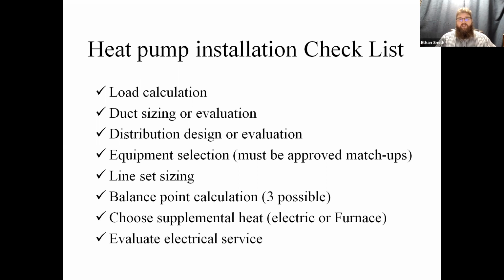The balance point, make sure you're figuring out how your customer wants to control their system. If they're looking for efficiency or if they're just looking to be comfortable. For years, I ran my system on what's called a comfort balance point, which is just a thermostat response. It would track when the heat pump wasn't quite keeping up anymore, and it would periodically bring supplemental heat just as a way to make it comfortable in the house. Works really good, not terribly efficient sometimes.